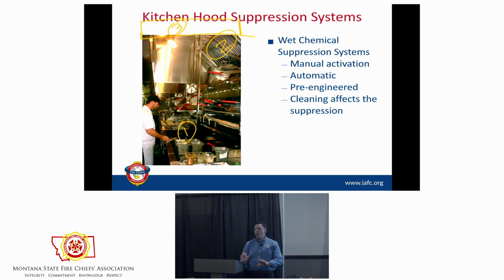It breaks. So if you poke above ceiling tiles on prevention inspections and you see grease, you have a leak in your exhaust duct, and you're probably going to get a fire in that area, right? Where's fire 4? The exhaust pipe, wherever that is. Where's fire number 5? Whoa. On the roof, right? Okay, so think about the roof, right? Combustible insulation, it's not supposed to be, but we've got insulation up against something that gets superheated.